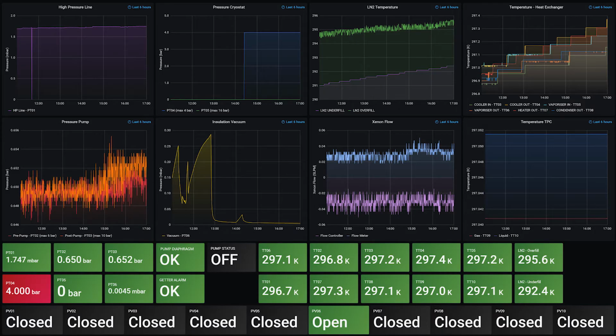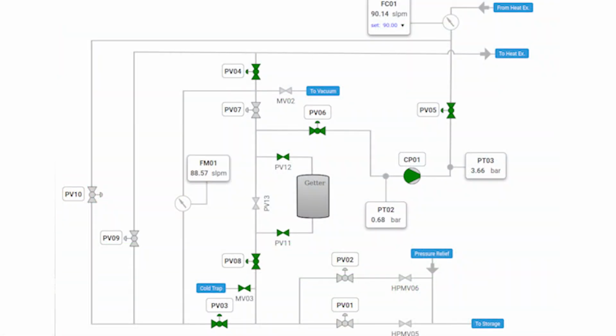For the demonstrator, we designed a comprehensive slow control system. The slow control is the brain of the detector facility, monitoring all parameters of the experiment. Our slow control uses open source software such as Grafana for the user interface, Prometheus for data ingestion and alarming management, as well as our own proxy service providing the necessary security level for the integration of the slow control to internet. This allows us to monitor the detector facility from anywhere in the world and even control remotely some sections of the gas system, such as the activation or deactivation of the purification loop, the adjusting of the recirculation flow, and if needed, the manual triggering of recuperation process.